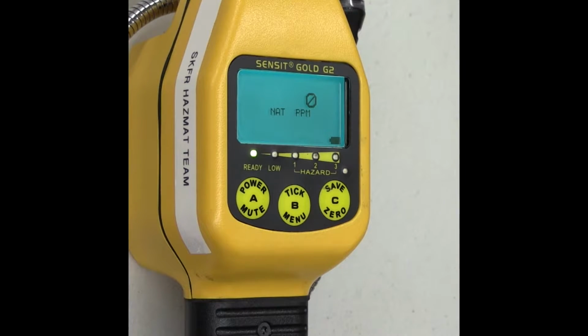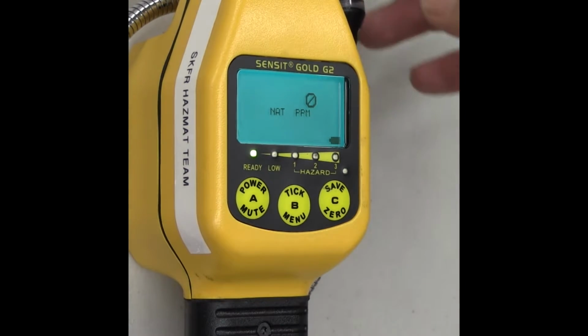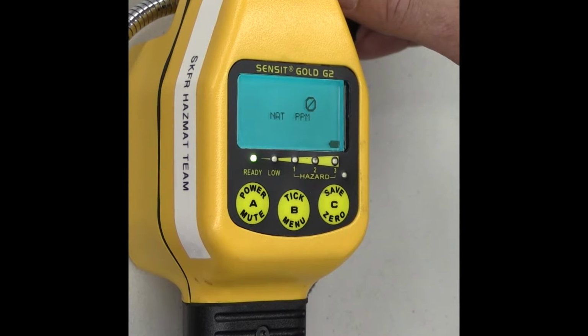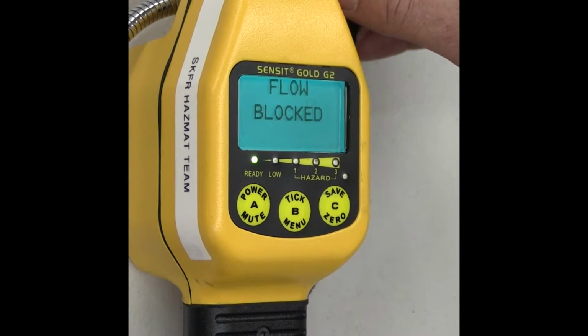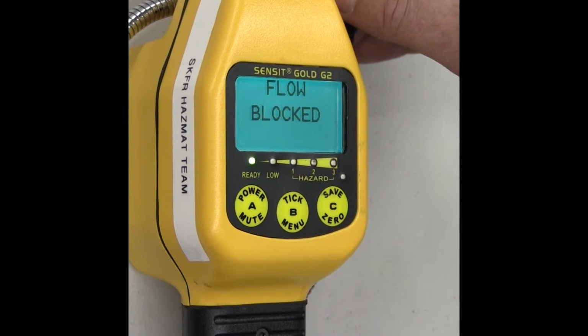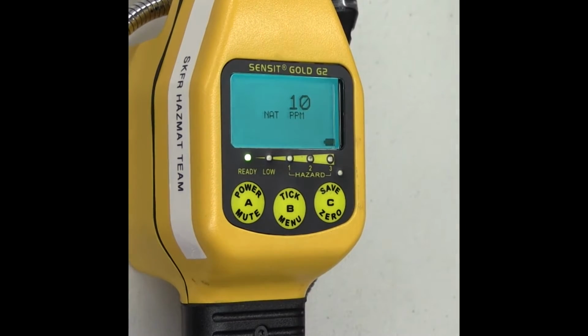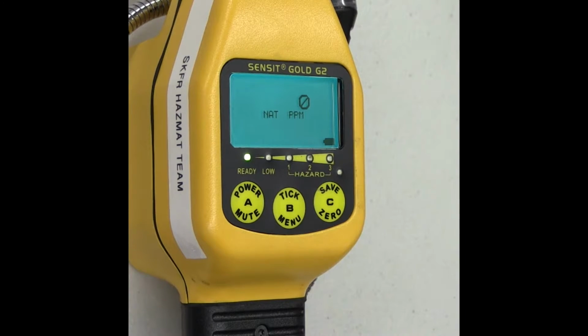Once the unit is warmed up, it's important to test the seal on the sensor cover. Do this by holding your finger over the wand opening. After a few seconds, you'll hear the pump slow down and the display will read flow blocked. Release your finger and the pump should go back to normal. If this does not happen, you're getting flow around the seals and need to tighten the cap or replace the cap and its O-rings.